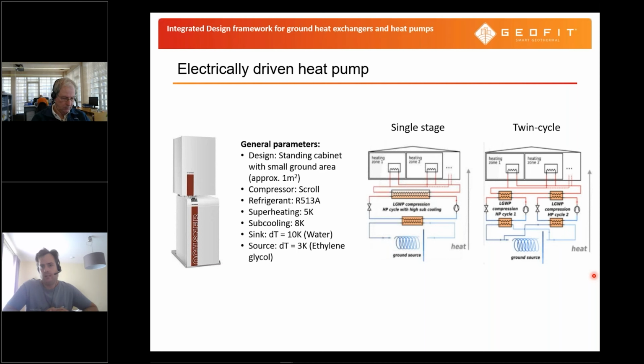One alternative is a single stage heat pump, which can use a significantly large condenser, which is shown here, having in mind a retrofit use case with higher supply temperatures and higher temperature spread on the heating side, which can make use of a higher subcooling, and that higher subcooling increases performance. So this can be realized with a significantly large condenser for such enhanced subcooling. Both systems allow a more efficient operation than, let's say, a state-of-the-art compression heat pump in the case of building retrofitting. And in the case of GEOFIT, we followed the approach of the large condenser.